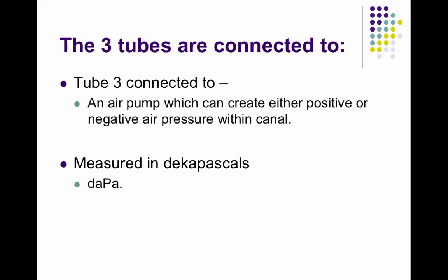Responses are measured in decapascals. The probe tone is placed in the ear canal, air pressure is pushed in along with a sound of 226 hertz, and the amount of energy emitted through the tympanic membrane as a function of different air pressures is measured.